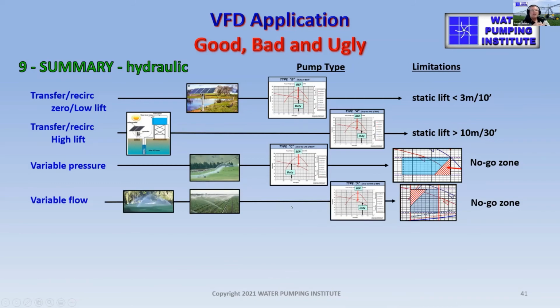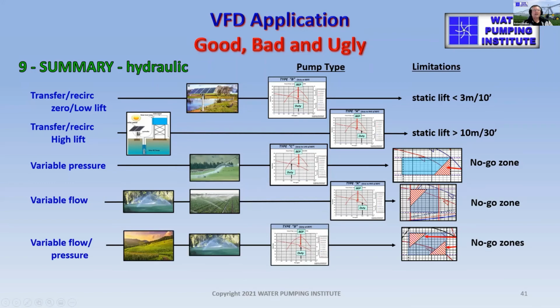The variable flow is your typical turf application, and it may be some ag situations. The best type of pump is the type A, where the duty is to the right-hand side, and you will have a no-go area on the lower flows and lower pressures. And lastly, the variable flow, variable pressure. The best pump would be a duty at best efficiency point, a type B pump, and you will have these no-go zones where you won't want to go. Now, not to say you can't go there. If you go there, two things will happen. You'll significantly reduce your energy savings from the application of the VFD, and you will expose yourself to damage of the pump.